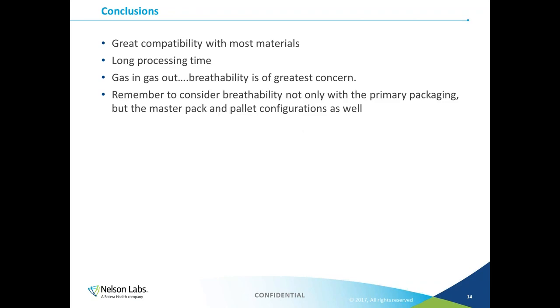In summary, EO has great compatibility with most materials — it does not react with or degrade most materials. It does have long processing times, but there are things we can do to mitigate this, such as increasing breathability of the packaging and taking into consideration load configurations on pallets. Again, this is a gas-in, gas-out process, and breathability is paramount.